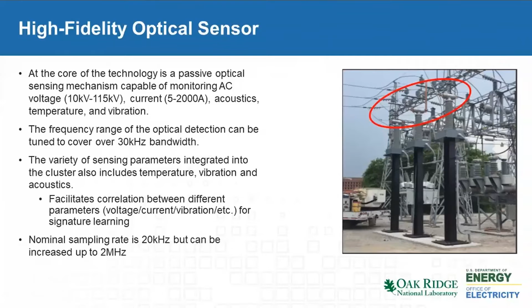Lawrence Livermore has installed a micro PMU device that measures magnitude and phase angle of voltage and current readings. To complement their readings, we have installed this sensor, which reads point on wave readings, or oscillographic waveforms. The combination of these two might be helpful for gleaning more about the events we're looking to detect and then mitigate down the road.